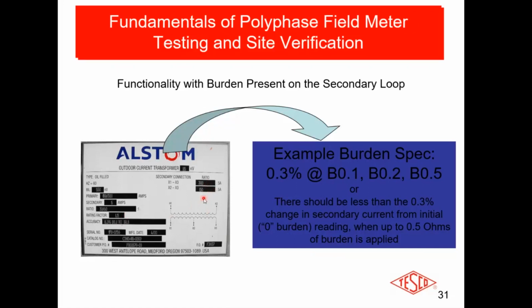The problem is anybody that has dual ratio transformers out in the field in any numbers, more than a few dozen, I will guarantee you that somewhere on your system there is a transformer that you think you wired one way, and it's actually wired the other way. And when I say you, I mean the billing system. So the billing system is set up one way, and you've actually wired it the second way. It may be that you're sending the customer half of the bill, or it may be that you're sending the customer twice the bill. All right?